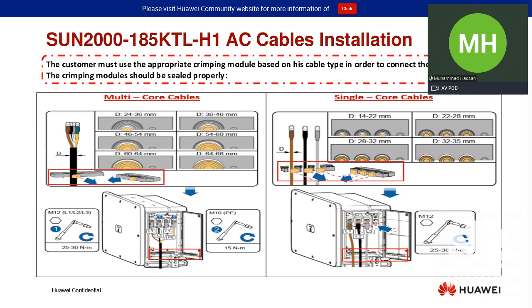Also, we are providing two types of glands to seal the AC compartments. If you are using the multi-core cable, you need to use the proper gland provided inside the AC compartment. You can take out the rubber tray, fix that cable inside that gland, and then tighten the AC compartment.